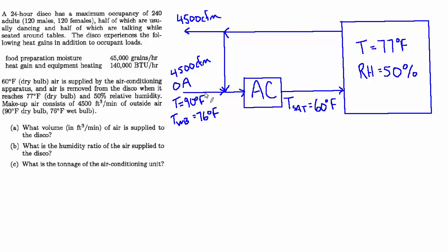So for the first part, part A, they want to know the volume in CFM of air supplied to the disco. For that, let's use our good old rule of thumb which says QS equals 1.08 CFM Delta T, with the understanding that when we use this formula we have to use the sensible heat load only, and the volume flow rate will go in with units of CFM, that's implied, and the Delta T will be the difference in temperature between the room and the supply air.